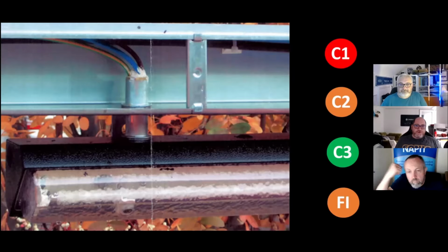Right, what's the solution with this? Basically what we ended up doing, where the bracketry system was, we put in new different types of lights, and we basically had a loop in, loop out on cable tray - armoreds on tray, it was armoreds. You can put the lights above them. No, we just had - all we did was have cable tray and we looped the cable up, basically into the bottom, out. So you've moved the cable entry position - it got moved to the bottom.